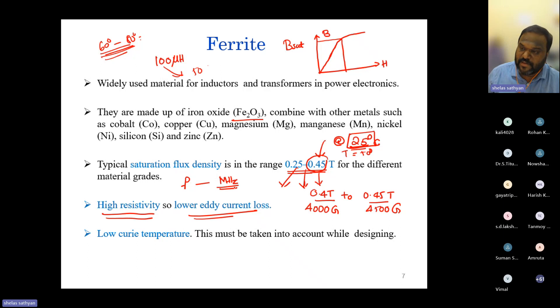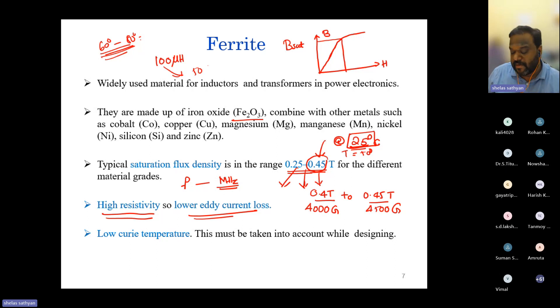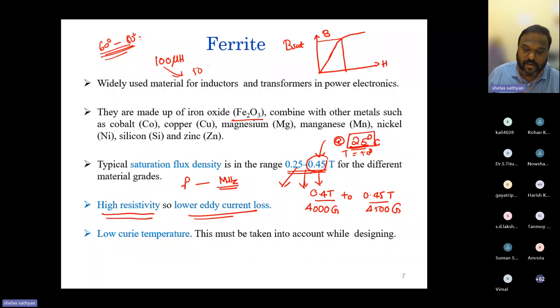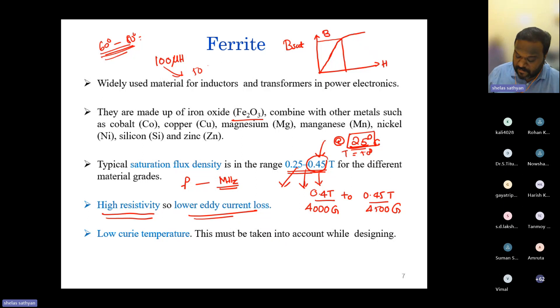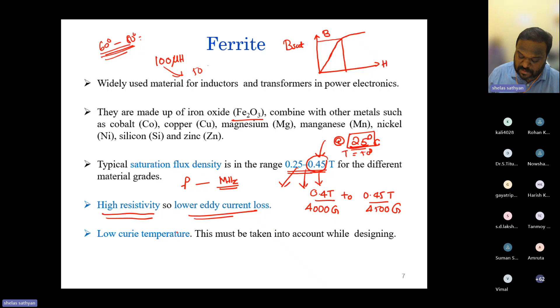In comparison, 50 Hz or 60 Hz silicon steel transformer cores can operate at maximum up to about 1 kHz. If you try to operate them above 1 kHz, they experience excessive heating due to increased core losses because the BH curve is quite wide. The ferrite core, having a very small BH curve and very low core losses, can operate efficiently even up to the megahertz range.